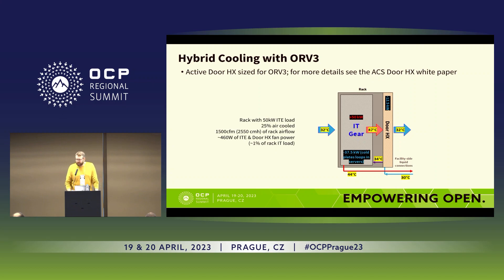These are the temperature variants we are looking at. There will be 32 degrees on the cold aisle; the IT gear heats the air up to 47 degrees, and then it is cooled back down to 32 degrees. That warm water then goes into the direct on-chip cooling. In the initial setup, we have a relatively low temperature of 44 degrees going out to the dry cooler. We want to see how high we can push that and how much usable power we get out of this. Any questions regarding that setup or suggestions?